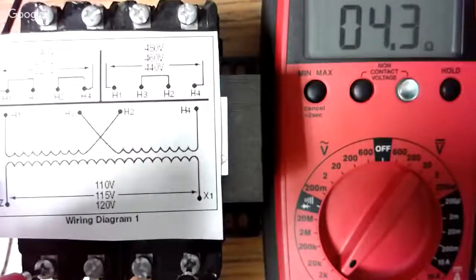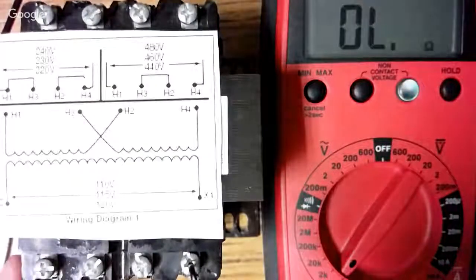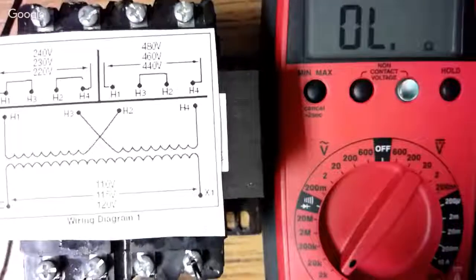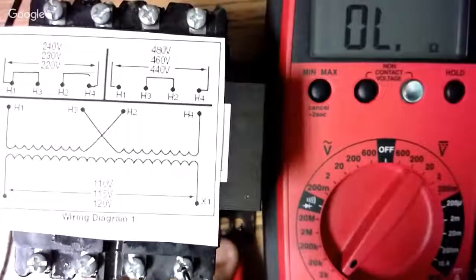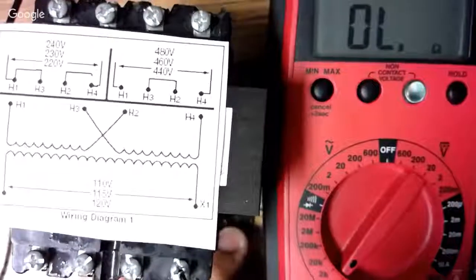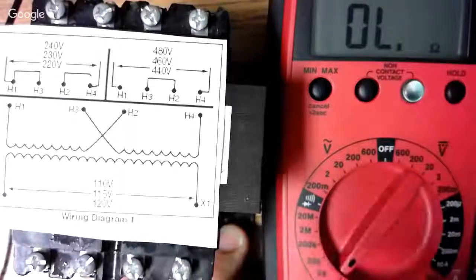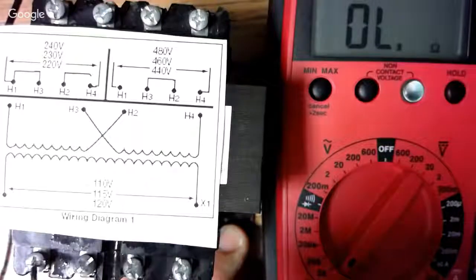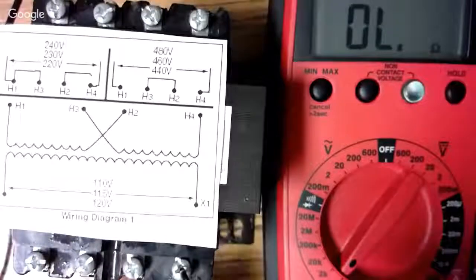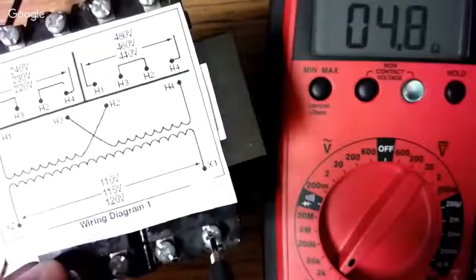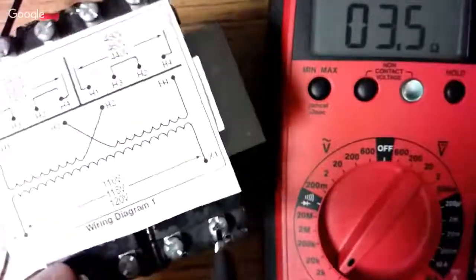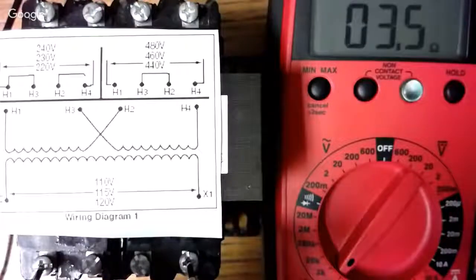Now I want to check this to ground. So I'm going to come over here and make sure it's not shorted to the frame anywhere. Try to find a piece of metal. Don't want to do it on the paint. And so, because I know there's continuity, I know this coil is good because I'm reading something. Reading something right there.